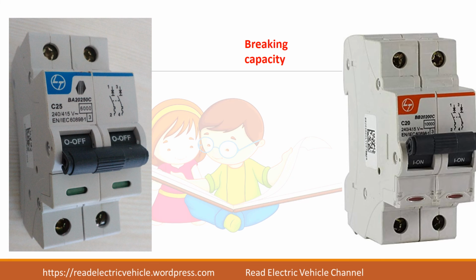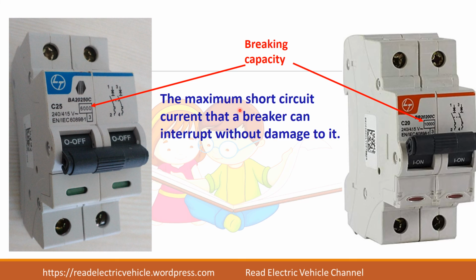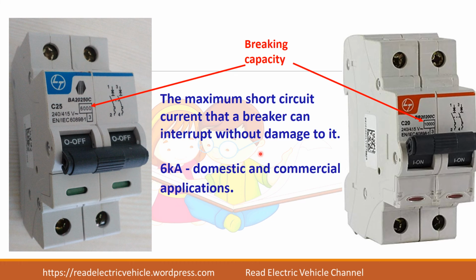Next we will see about the breaking capacity of the breakers. Here 6000 is written in a box. Here it is 10,000. It means that this is 6 kilo amps and this is 10 kilo amps. That represents the maximum short circuit current that the breaker can handle without damage. So this 6000 amps or 6 kilo amps is suitable for domestic and commercial application. For industrial application, we have to go for a higher short circuit current, because in a residential building, normally the maximum fault current will be less than 6 kilo amps. So this type of breaker is preferred. But if the load is very high, like in industry, the short circuit current may be very high. In such cases, you have to go for a higher rating.